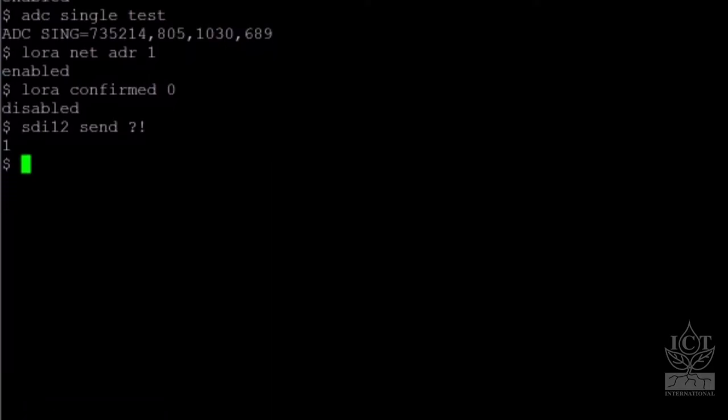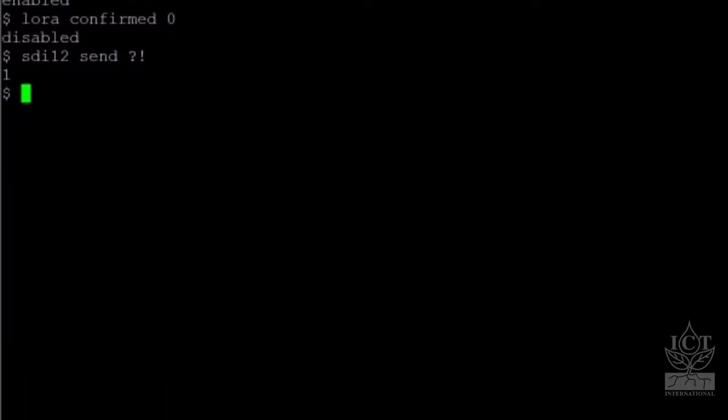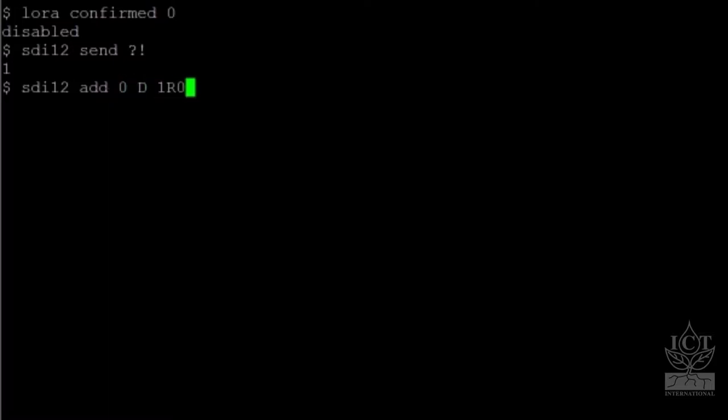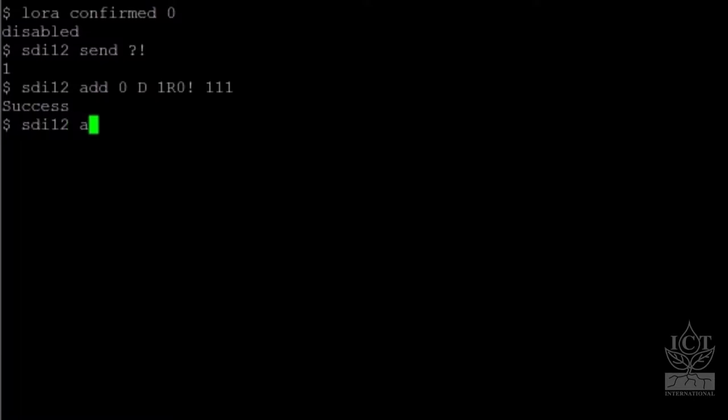To add an SDI-12 measurement, use the command SDI-12 ADD. For a result measurement with three results, use the command SDI-12 ADD 0 D 1R0 111. This adds the command 1R0 to the SDI-12 command slot 0. To activate the SDI-12 command, enter SDI-12 ACTIVATE 0 1.